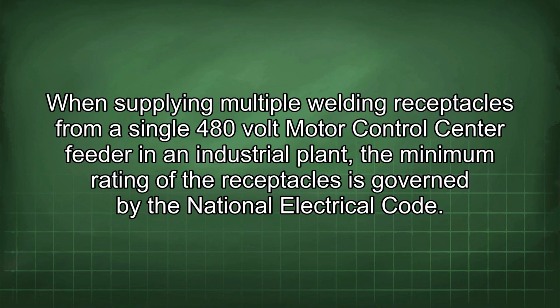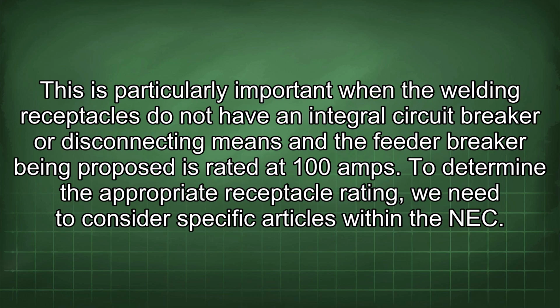When supplying multiple welding receptacles from a single 480-volt motor control center feeder in an industrial plant, the minimum rating of the receptacles is governed by the National Electrical Code. This is particularly important when the welding receptacles do not have an integral circuit breaker or disconnecting means and the feeder breaker being proposed is rated at 100 amps. To determine the appropriate receptacle rating, we need to consider specific articles within the NEC.